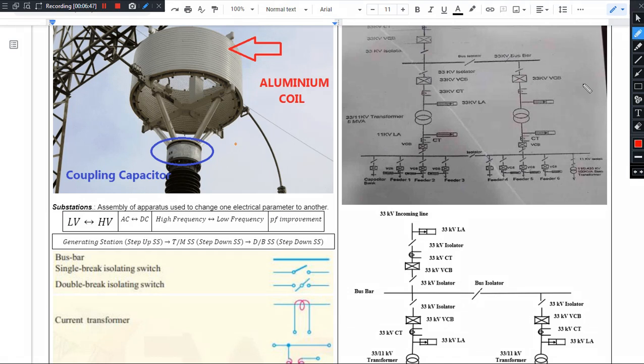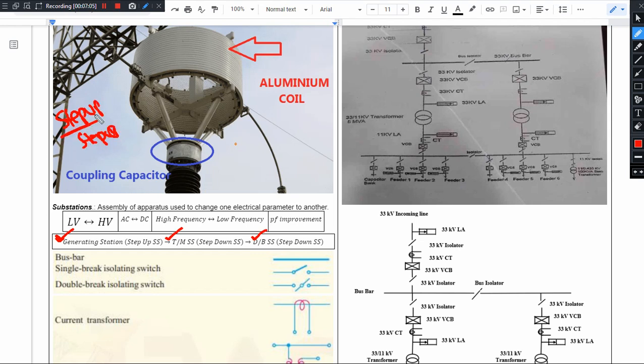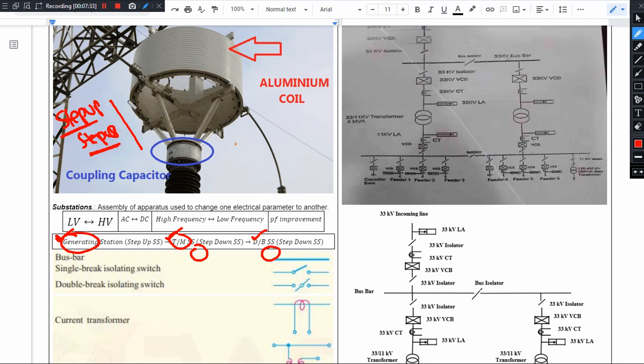Substations are basically of three types: generating substation, transmission substation, and distribution substation. Step-up transformers are used at generating stations and transmission substations, while step-down transformers are used at transmission and distribution substations. Transmission substations include both step-up and step-down transformers, making them the interlinking stations between generating stations and distribution substations.